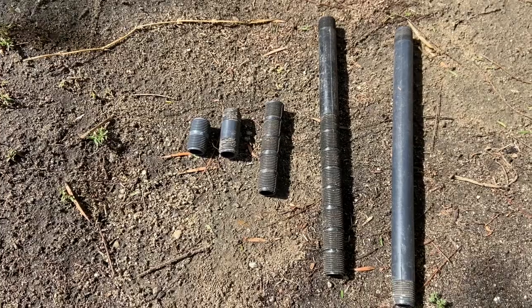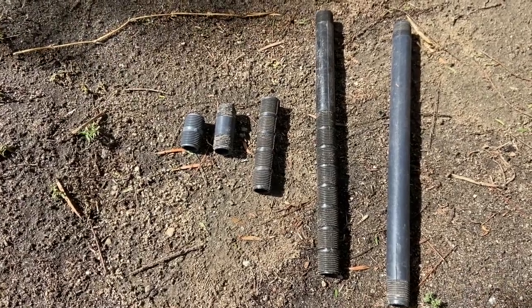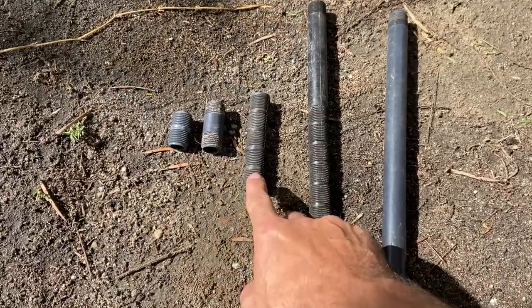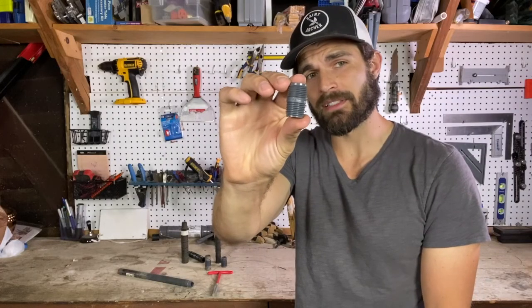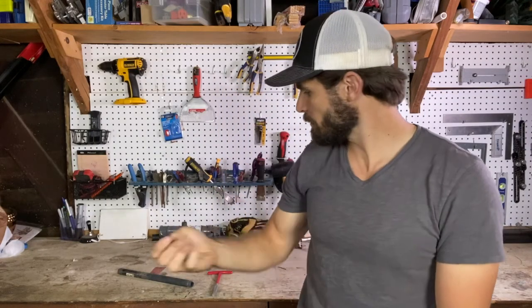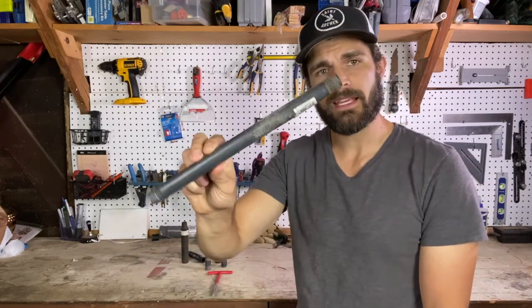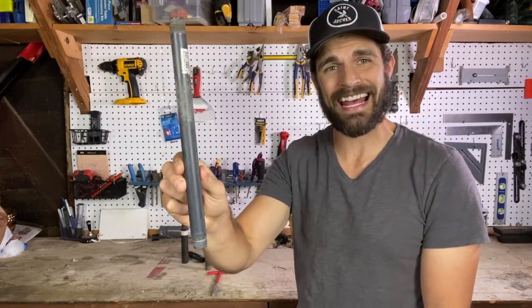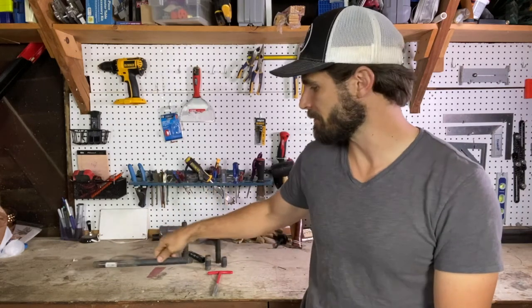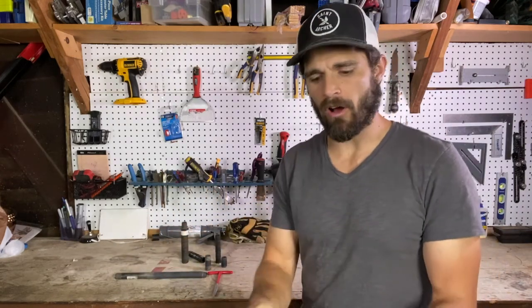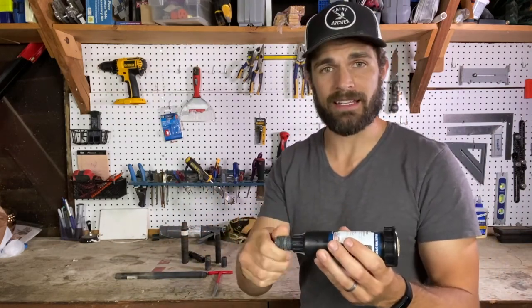Now, when you were pulling out that sprinkler head to replace it the first time, it's very possible that one of these little guys came out along with the sprinkler head. These can come in a couple of different sizes. This one, which is pretty short, or they can come in over a foot long and add additional height onto your sprinkler system.